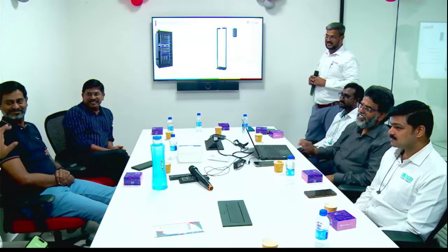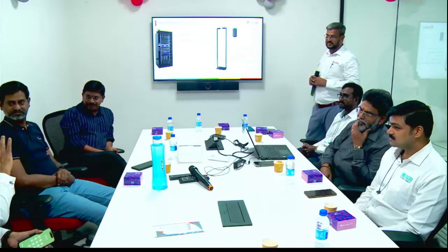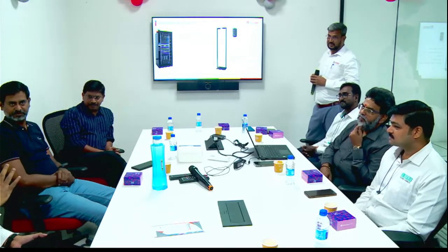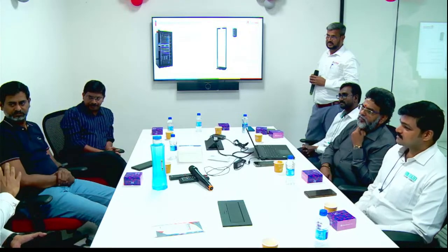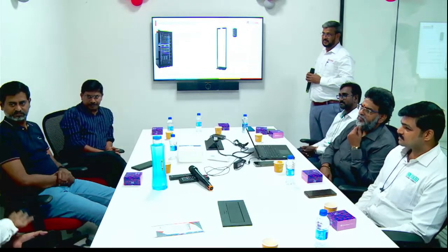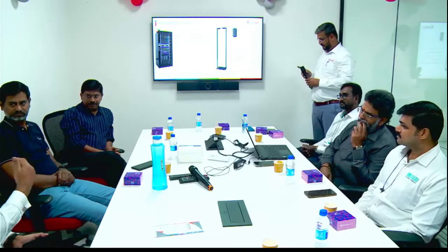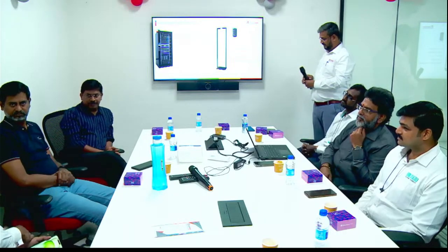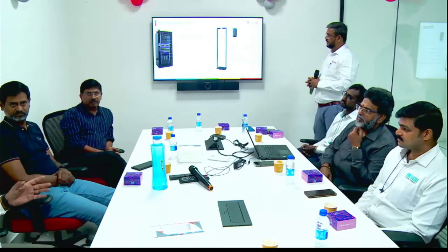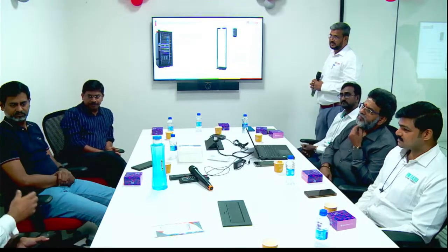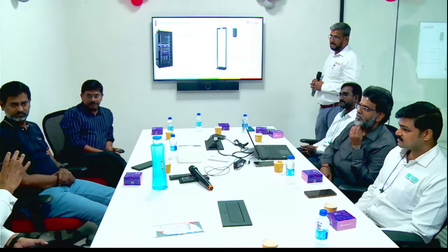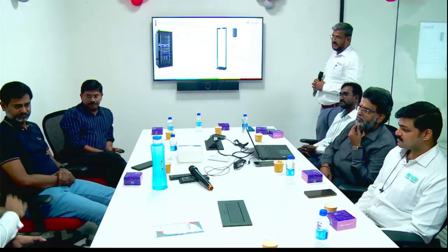So this is again, we have put a demo. Actually, this is a prefabricated data center for you. It is available in single rack format, and it can go up to any kind of rack capacity you require with the respective cooling. It starts with a minimum of 3.5 kilowatt. It can go up to around 20 kilowatt with multiple methods. We have got here today up to 45 kilowatt. So one rack you can gather up to 40 kilowatt, with the single method. That's the size of the computing if you are putting inside the rack. So U space depends upon what kind of component you are putting inside, basically.